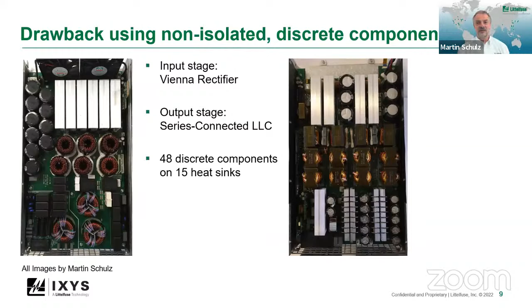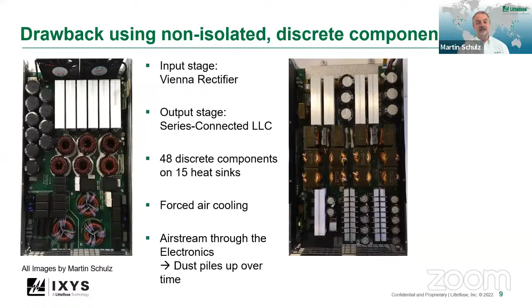It features forced air cooling, which brings 2 disadvantages. One, you need fans, and the other is the airstream goes through the power electronic section, not only covering the heatsink but all the power electronics. That means dust piles up over time. Dust or dirt piling up in power electronics degrades the thermal performance, which leads to degrading performance of the drive itself, and in turn regular maintenance becomes necessary.